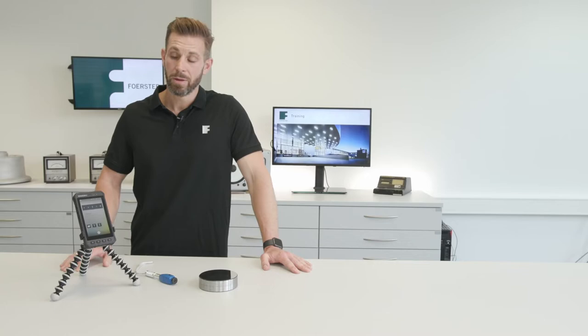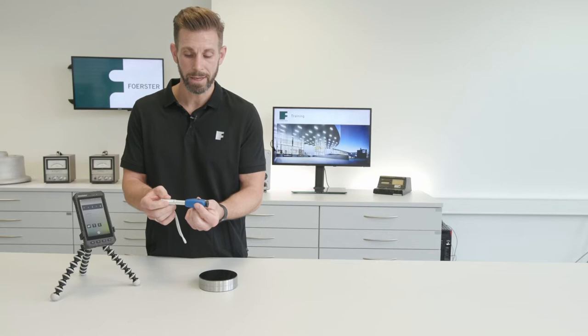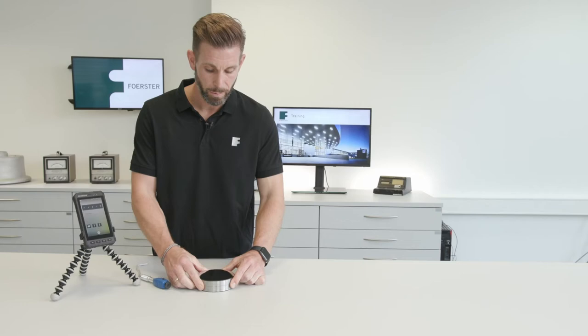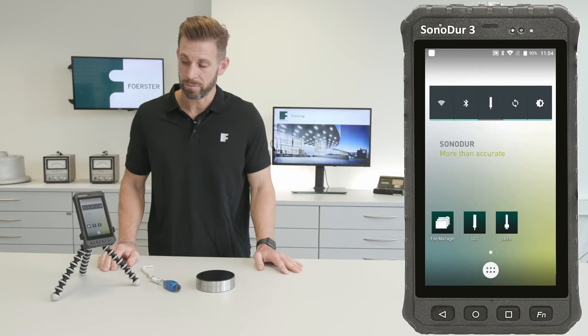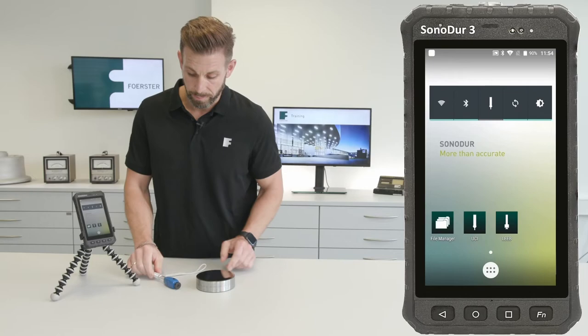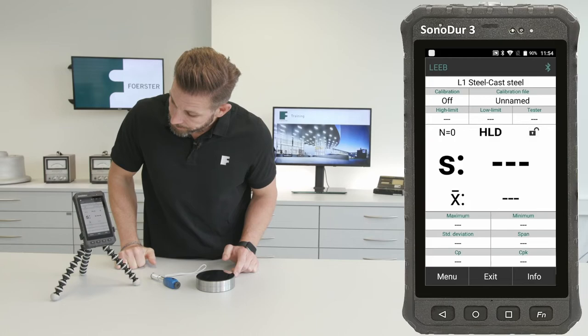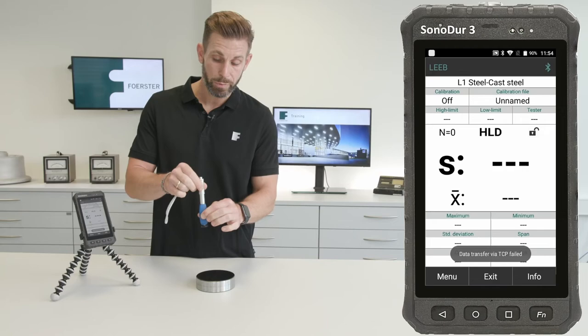Let's take a look in practice. We have our SonoDur 3 device for displaying and receiving the data from our probe, and we have a little Leeb probe here — an HLD probe — and a hardness block with a value of 634 HLD. We have to connect that device with the SonoDur 3 via Bluetooth. I'll start the connection by pressing this button and open my Leeb app. The device says it's connected and we can straight away start making measurements.